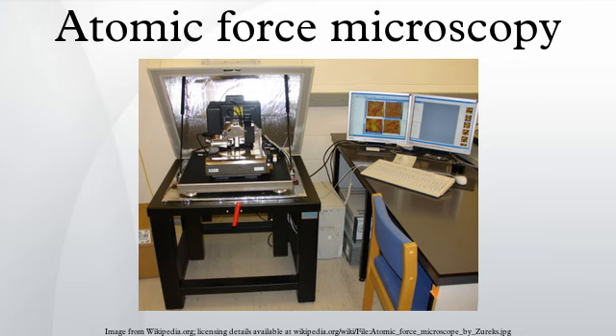AFM images can also be affected by nonlinearity, hysteresis, and creep of the piezoelectric material and crosstalk between the X, Y, Z axes that may require software enhancement and filtering. Such filtering could flatten out real topographical features. However, newer AFMs utilize real-time correction software or closed-loop scanners, which practically eliminate these problems. Some AFMs also use separated orthogonal scanners, which also serve to eliminate part of the crosstalk problems.